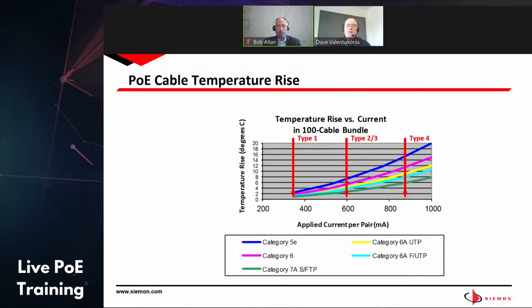So what happens is, depending on the amount of current you apply - whether it's Type 1, which is 15 watts, Type 2 or 3, which is 30 and 60 watts, or Type 4, which gets up closer to 90 watts - you have a temperature rise in the cable bundles. And it changes depending on the category of cabling.